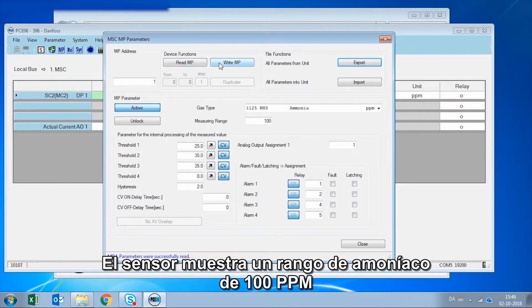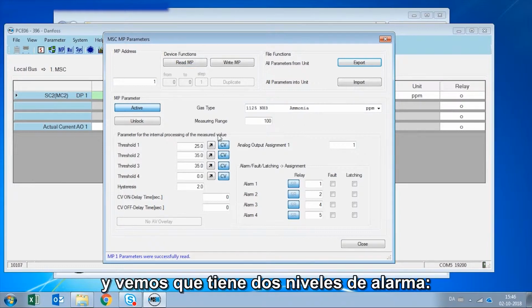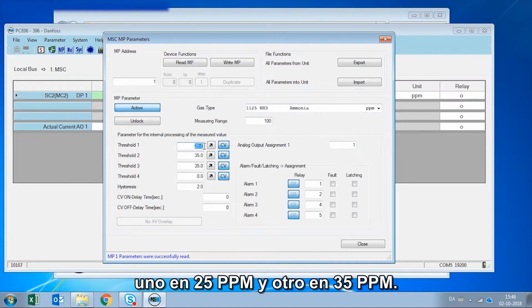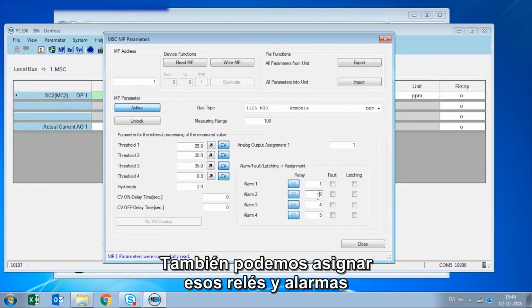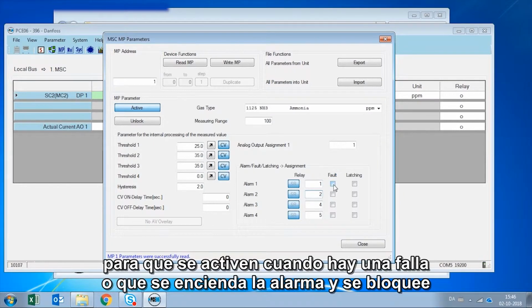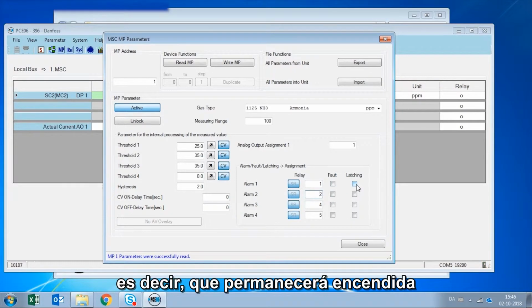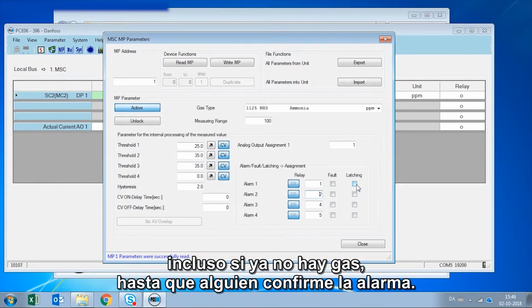The sensor is an ammonia, 100 ppm range, and we can see that it has two alarm levels, one at 25 ppm and another at 35 ppm. The way that these alarms react is alarm 1 activates relay 1 and alarm 2 activates relay 2. We can also assign those relays and alarms to be activated when there is a fault, or have the alarm latching, which means that it will stay on regardless if the gas is gone until someone acknowledges the alarm.